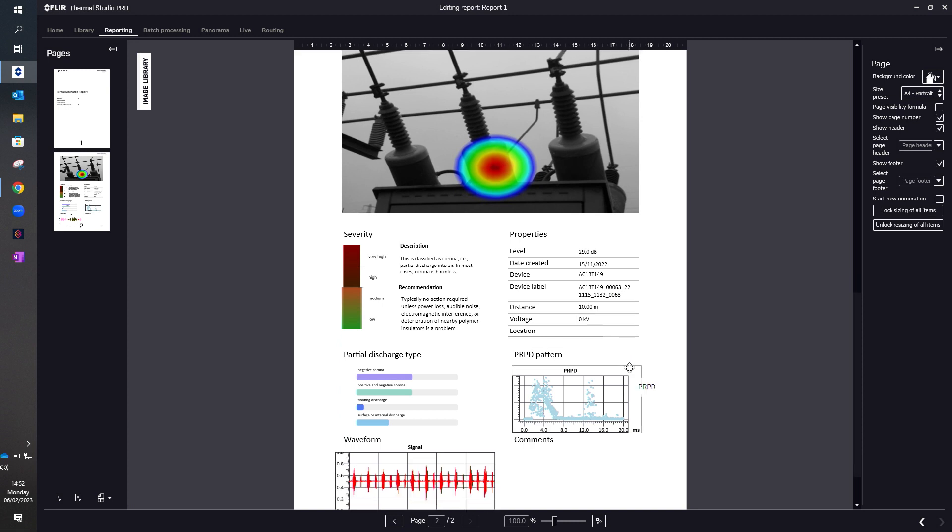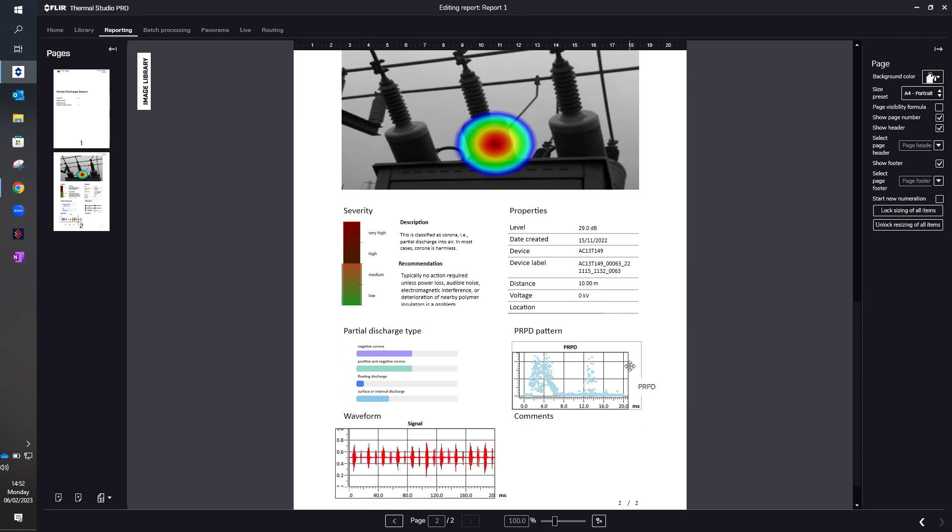We also move down to other parameters within the partial discharge application. This useful section here, partial discharge type, tells you whether it's negative corona, positive and negative corona, floating discharge, or surface or internal discharge.